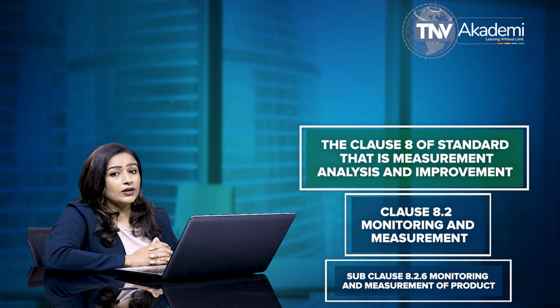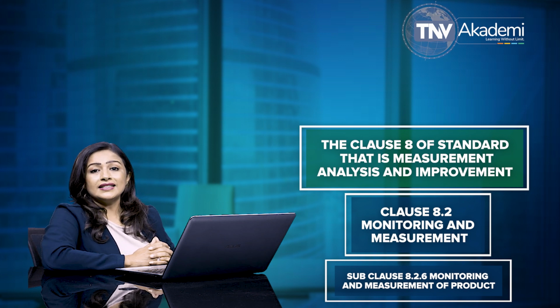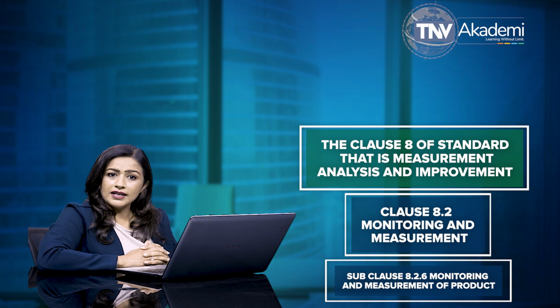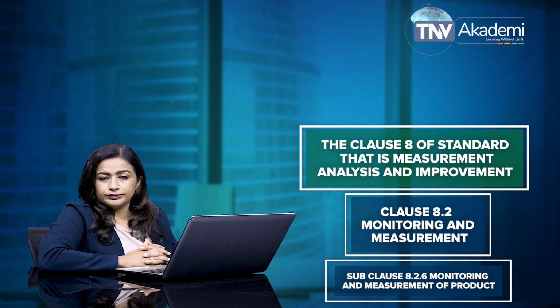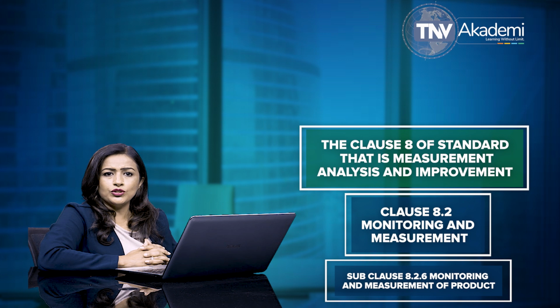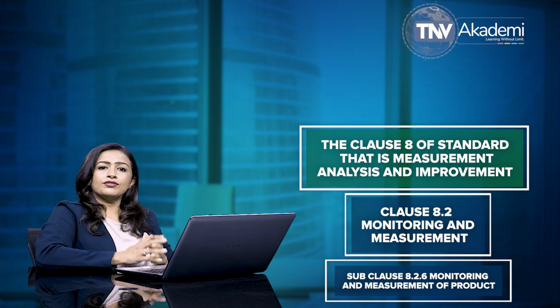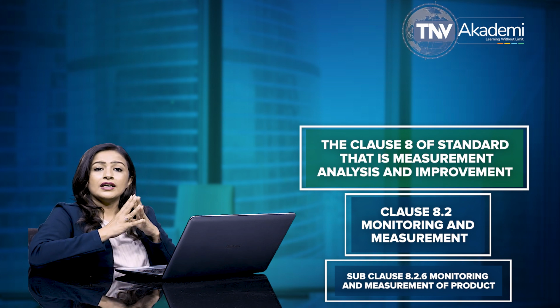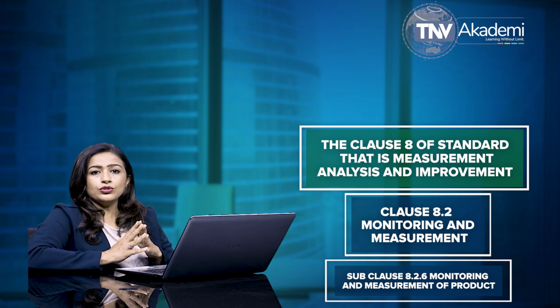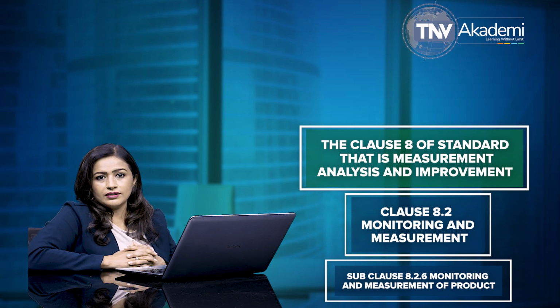organization. The organization must record the identity of the person authorizing release of the product. According to this clause 8.2.6, appropriate records must identify the test equipment used to perform measurement activities.